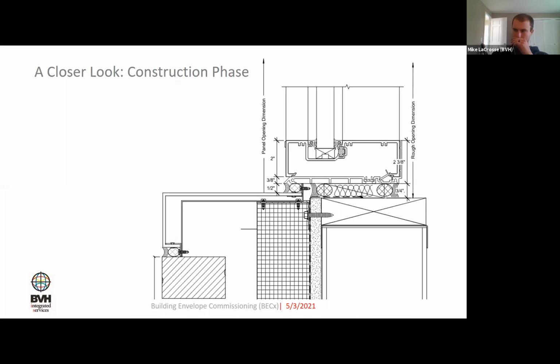I want to talk about general construction phase testing. On most projects where we're commissioning, testing the installations is a huge part of the commissioning process during construction phase. At this point the design is complete and the building is in active construction. Testing is important because it can identify one of two or three things.